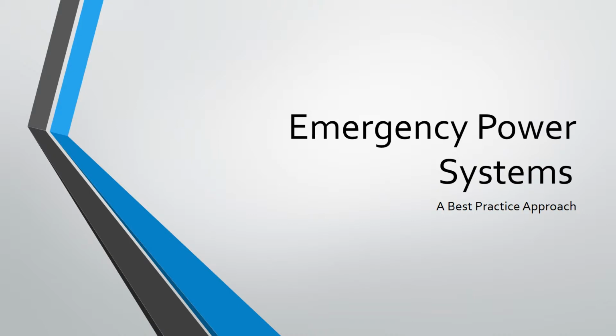It's a very important thing to know, because very often, many hospitals are meant to have redundant power feeds to their hospital, but in many cases they're fed from the same substation. And substations will and do have problems. And so even if you have two feeds coming from different parts of the property, if it's from the same substation, and a substation has an issue, obviously you're going to lose power, and you're going to be on generator.